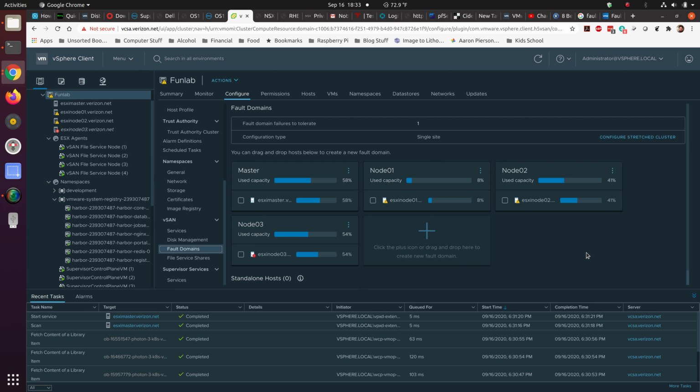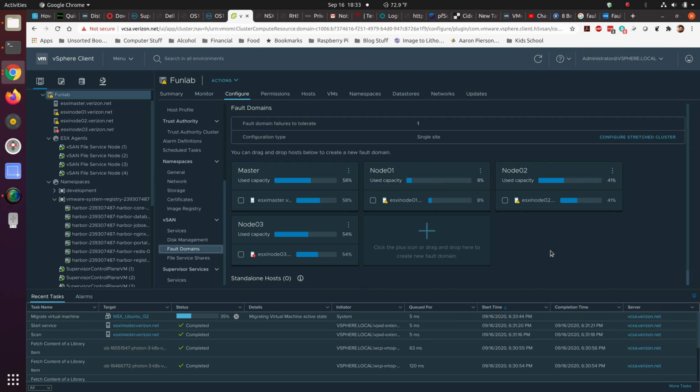If you want to get up to a failure to tolerate of 2 or 3, then you need to have, I believe, 6 or 7. I think 5 is where you can tolerate 2 maybe, but 6 or 7 is where you start to get into the fault tolerance of 3. And that's where you start looking at what servers are connected to what PDUs and what PDUs are connected to what breakers. Really a physical view into how your physical infrastructure is set up, and then mapping that so that your logical systems are going to withstand any failures in the physical realm.